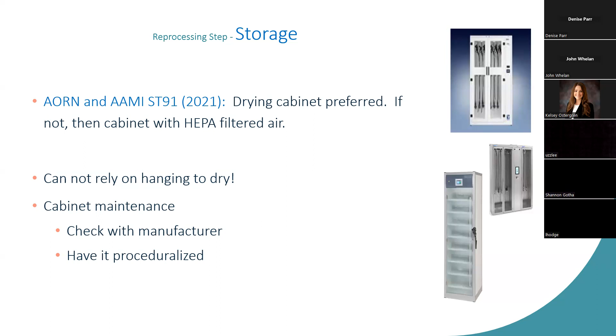I still find it at healthcare institutions where they have very nice looking laminate cabinets with passive airflow. Those days are gone, and this is not new information in the last few years. This has been for a while. There needs to be HEPA filtered air blowing into the cabinet. And you can't rely on hanging to dry the scope. When it comes to cabinets, you also have an IFU from the manufacturer of the cabinet that you have to follow.